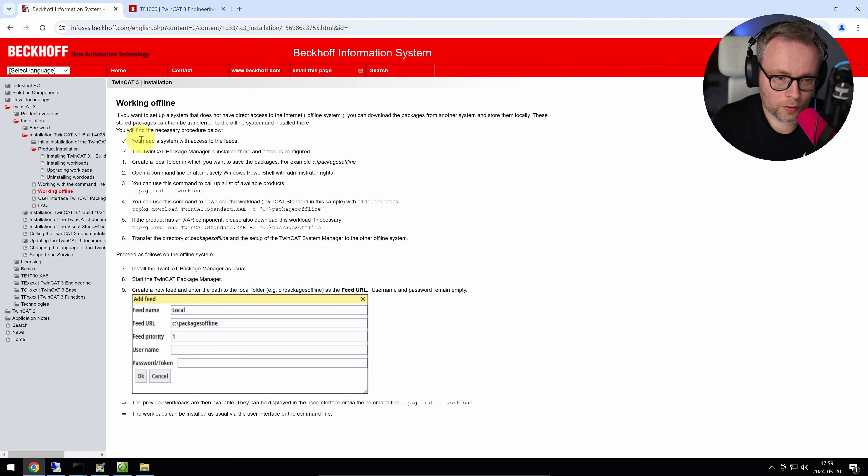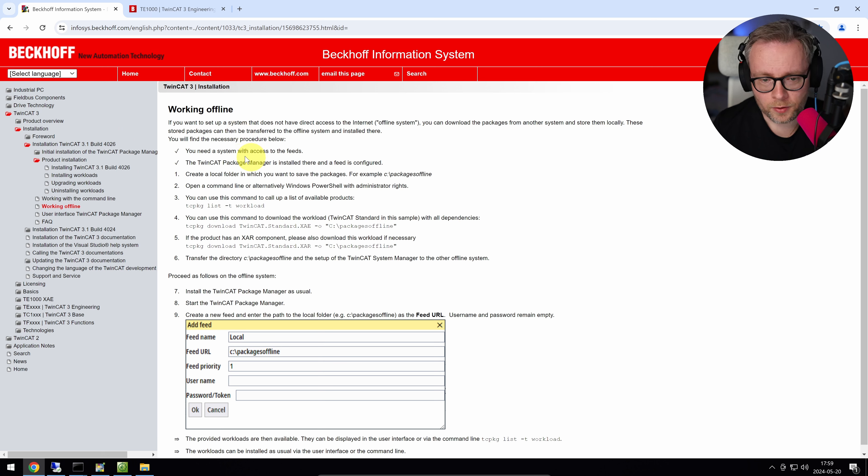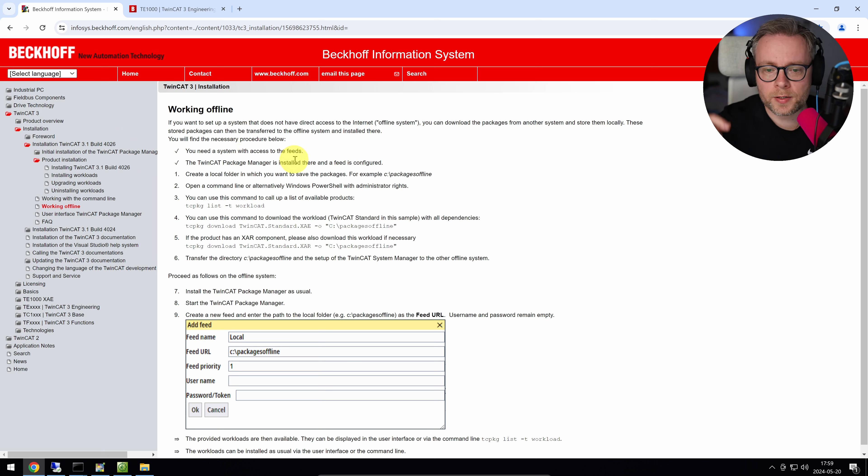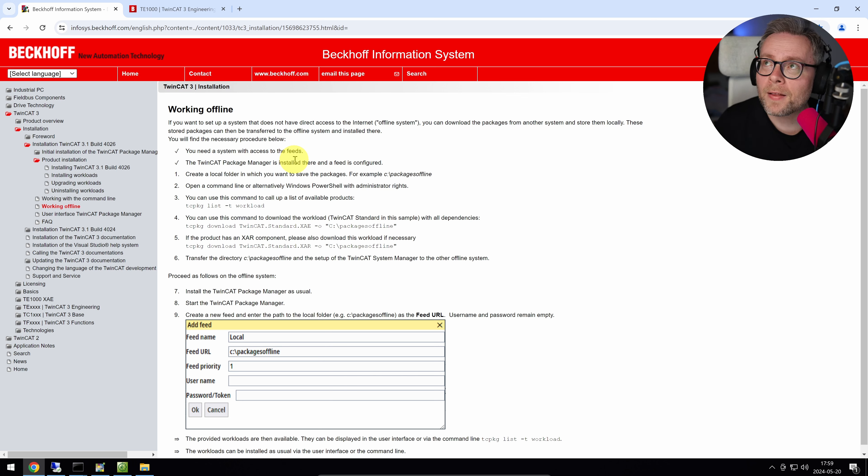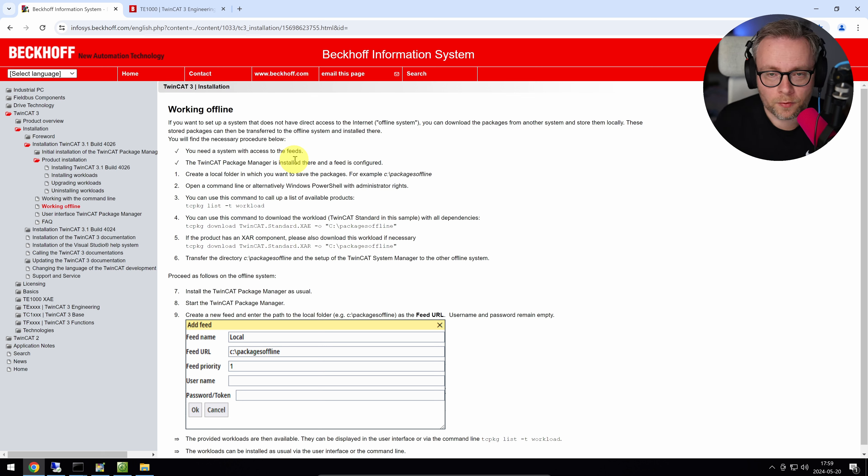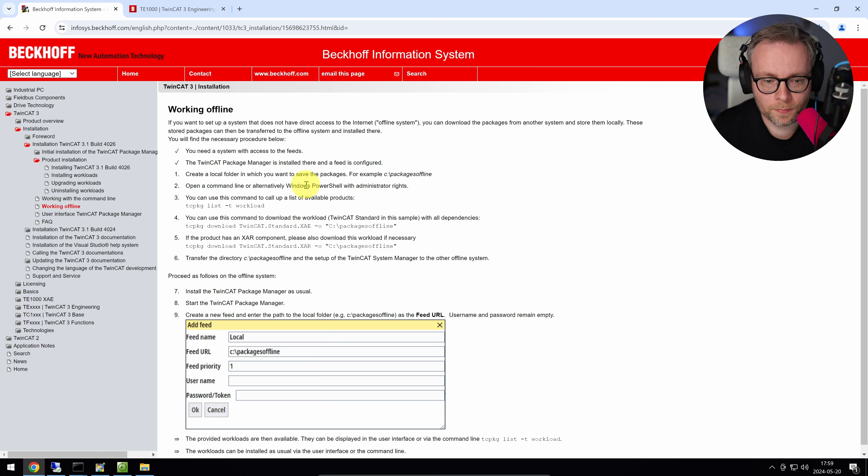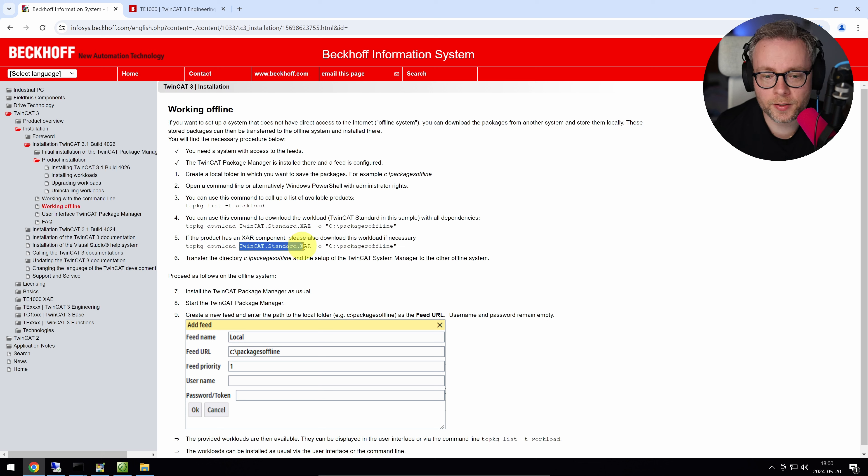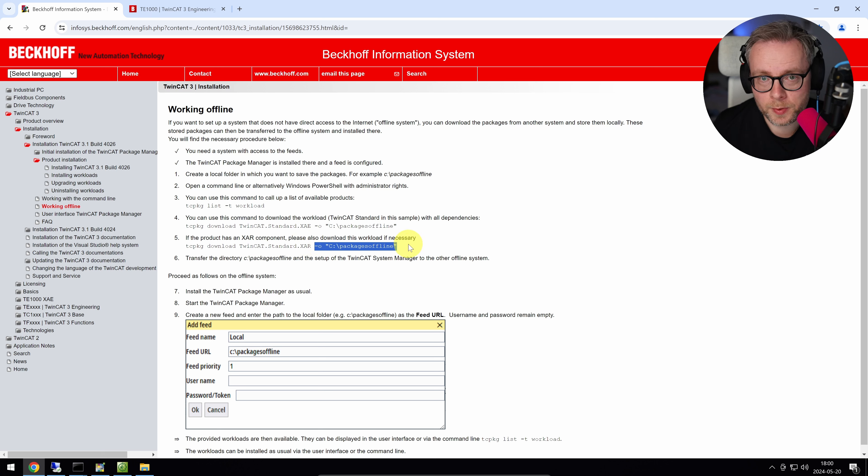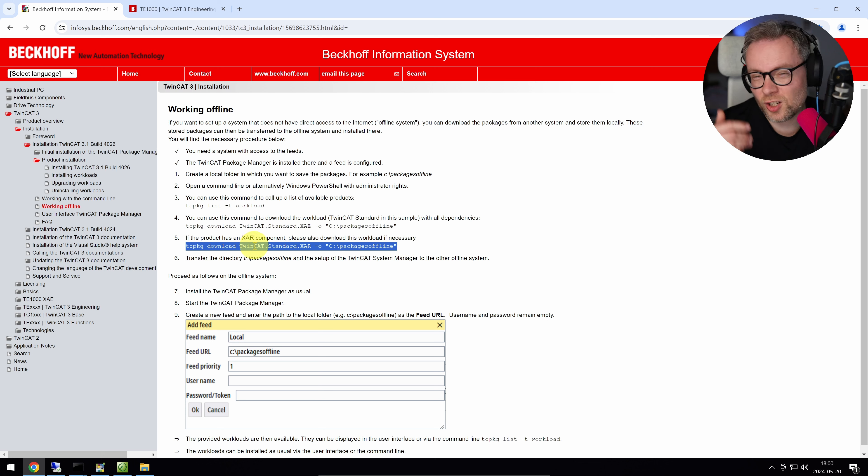So I've downloaded the package manager on the USB stick, but that's not enough. We need to download everything related to the XAR, the runtime as well. And Beckhoff has a very good document for this called Working Offline. It basically says that you need to have the system with access to the feeds. So what they're referring to here is that we need a computer that can download the packages. So this is my development environment. My development environment has access to internet, so I can download all packages and prepare them for the target runtime, which doesn't have internet. And what I can do is that I can download all my packages related to the XAR. So the workload for the XAR to a device. So in this case, the USB stick.